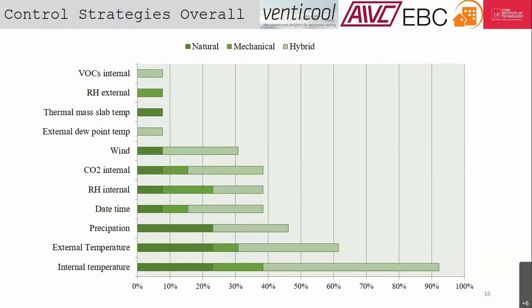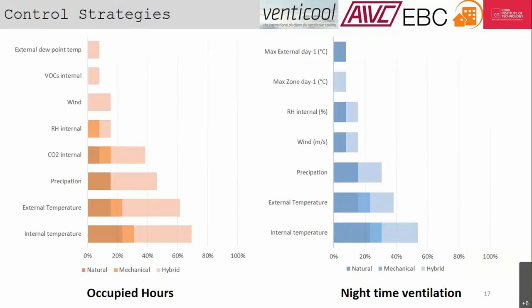We had one example with a fully manual control strategy with no internal temperature input. Breaking that out in terms of occupied hours and systems using daytime or nighttime ventilation, internal and external temperature remain common parameters. There are very few examples where VOCs or external dew point temperature are used during occupied hours, and very little use of max external day temperature or max zone day temperature from the previous day in control strategies to update set points.